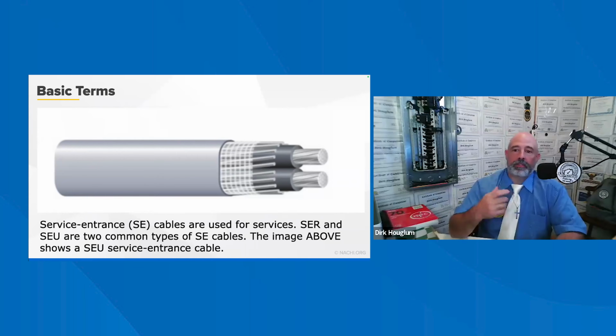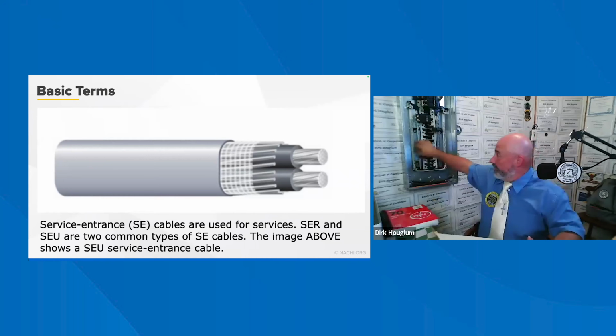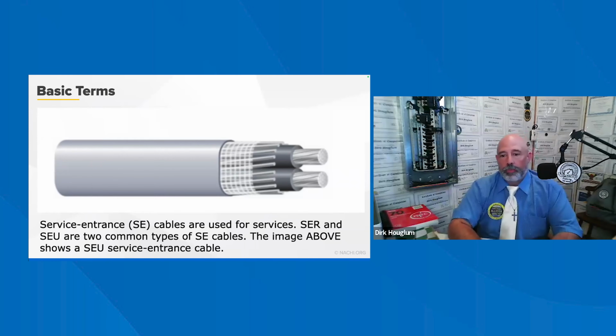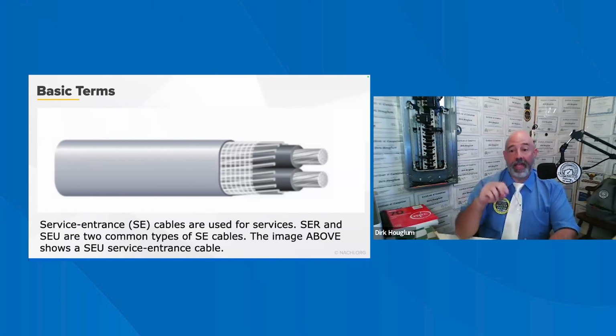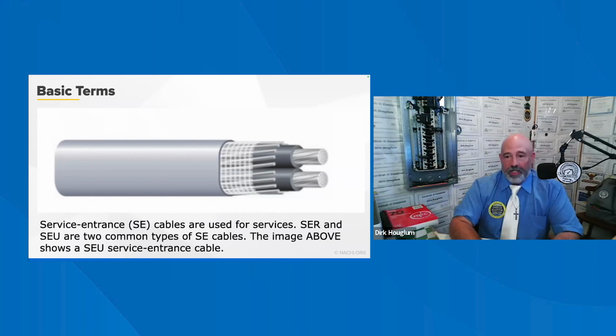The panel board contains bus bars. That's what these are here. Terminals, overcurrent protection devices, and mounting hardware designed to be enclosed in a cabinet or box. In residential wiring, the panel board is usually not distinguished as a separate piece of equipment from its cabinet, because it's normally installed inside the cabinet enclosure at the factory. A receptacle is a contact device installed at the outlet for the connection of an attached plug. So a receptacle outlet is an outlet where one or more receptacles are installed.